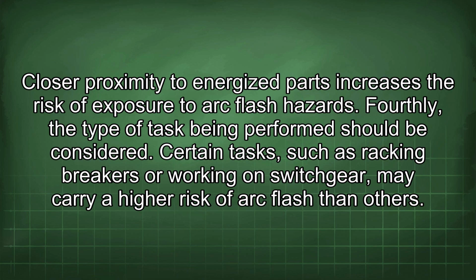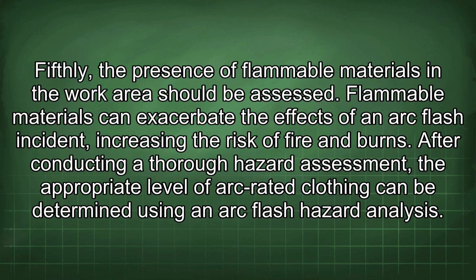Fourthly, the type of task being performed should be considered. Certain tasks, such as racking breakers or working on switchgear, may carry a higher risk of arc flash than others. Fifthly, the presence of flammable materials in the work area should be assessed. Flammable materials can exacerbate the effects of an arc flash incident, increasing the risk of fire and burns.